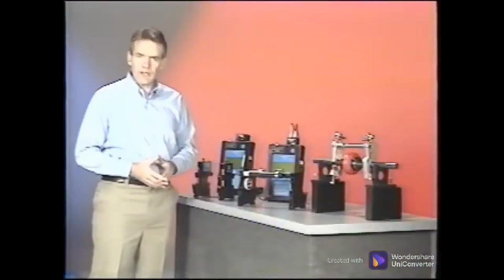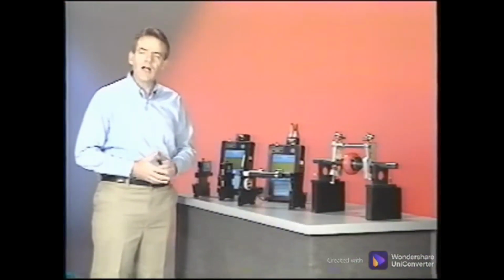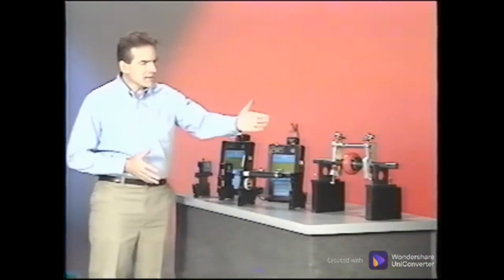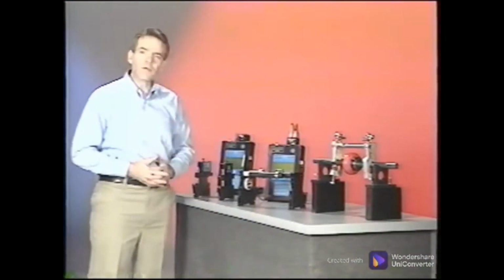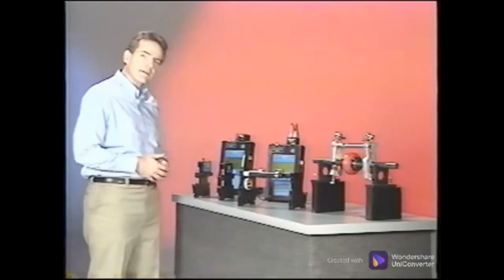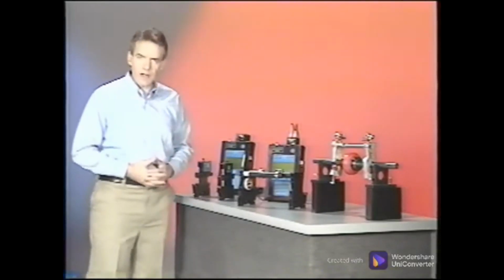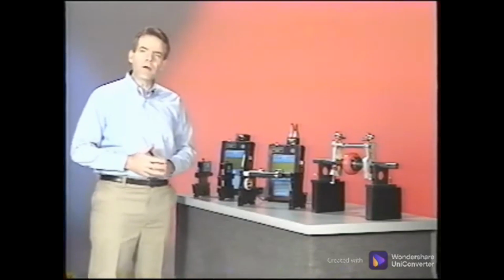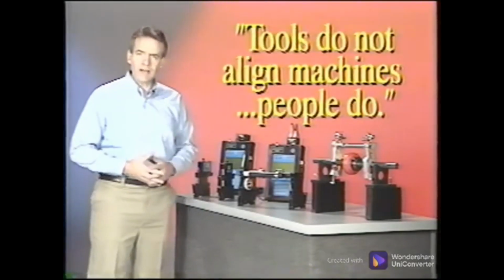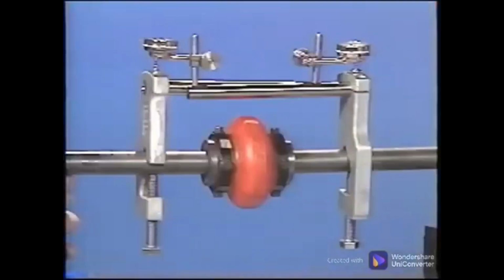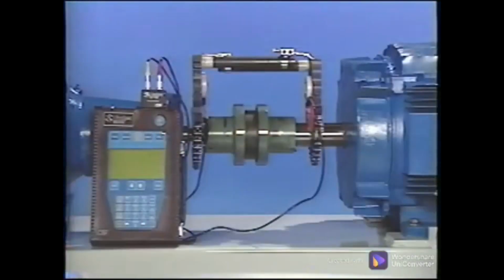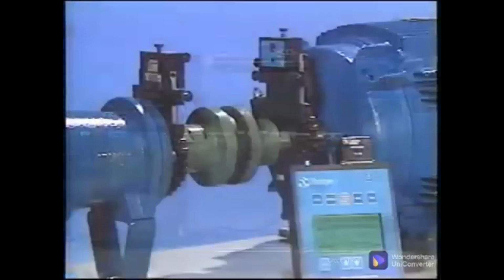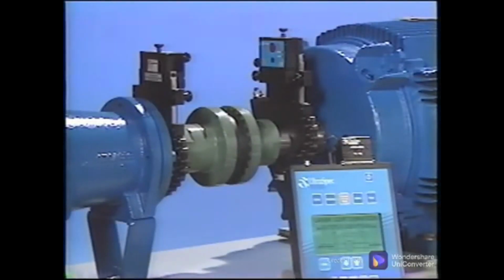If you were to hire a contractor to align a machine, would you get better alignment from a dial indicator set that costs a few $100s, or a laser set that costs tens of thousands of dollars? The key to remember is, tools do not align machines, people do. The tools are merely used to measure the alignment condition, and some tools help calculate the machine moves, but the better tools help a competent person to perform the same job faster and with less risk of error.